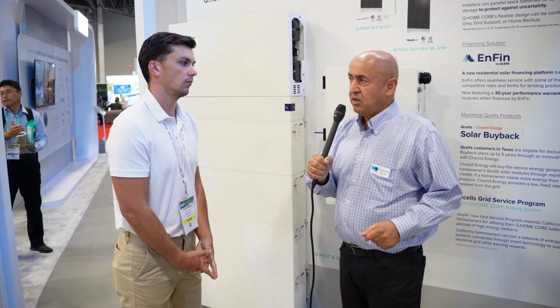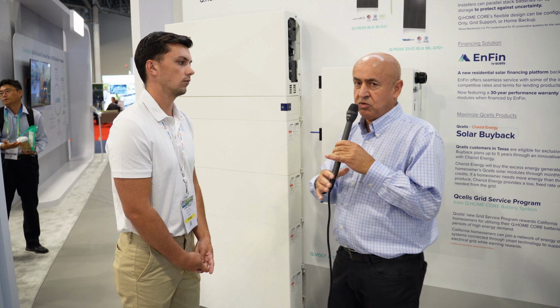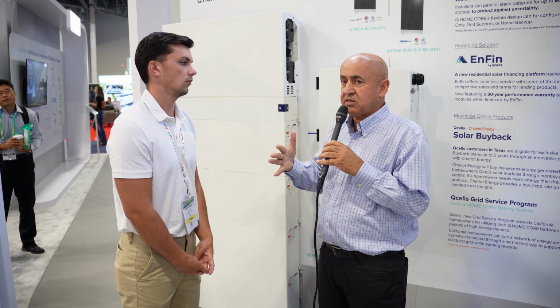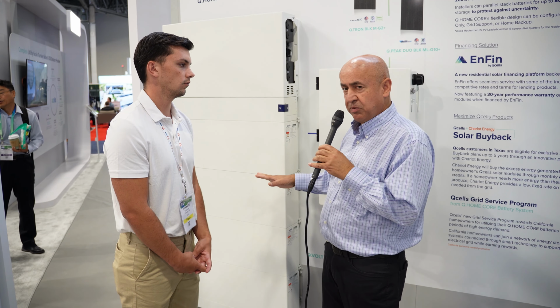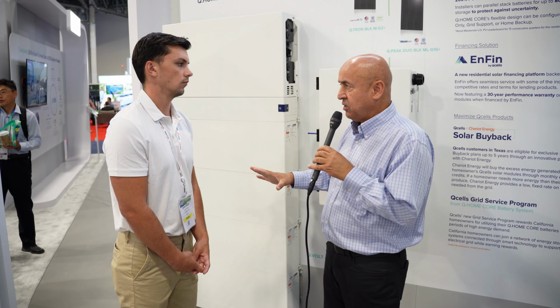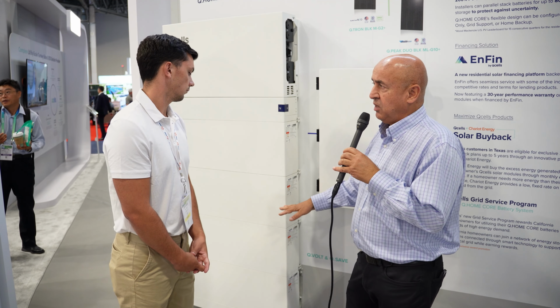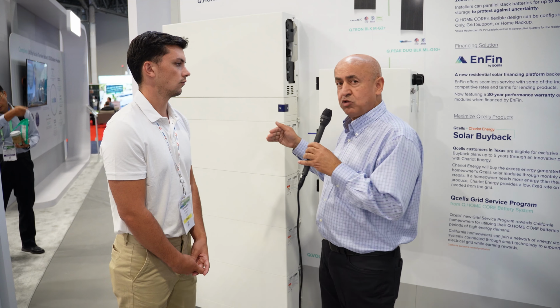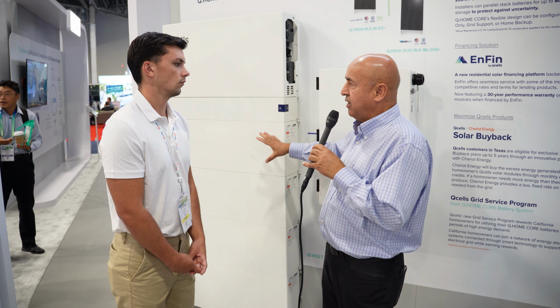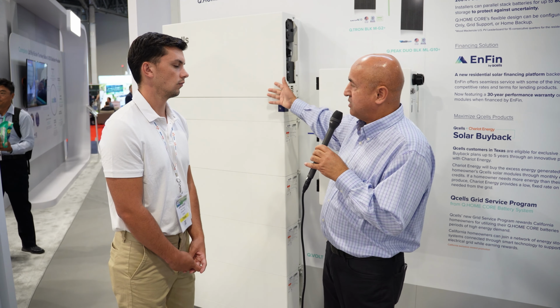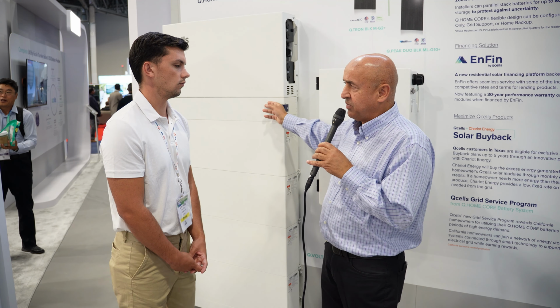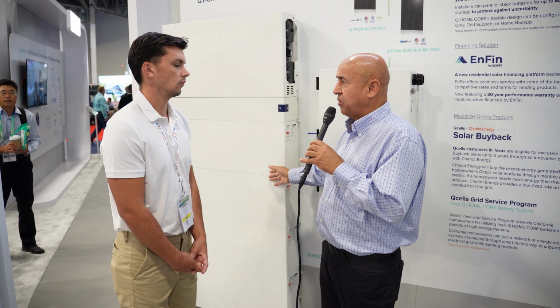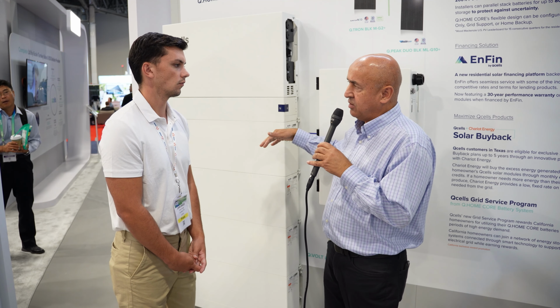That's a good question. The system is designed to basically add a battery in the future. That is technically feasible. Obviously the installer or homeowner would need to take into account the placement of the system and make sure there's enough room to grow and add a battery module. You would basically take off the inverter and the BMS, the battery management system, install a battery module, then put it back together and update the firmware.